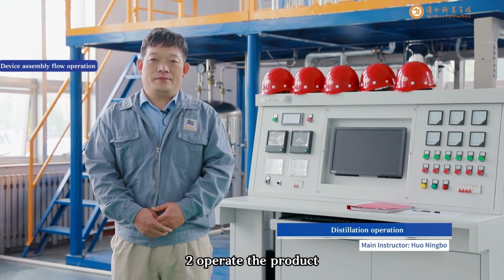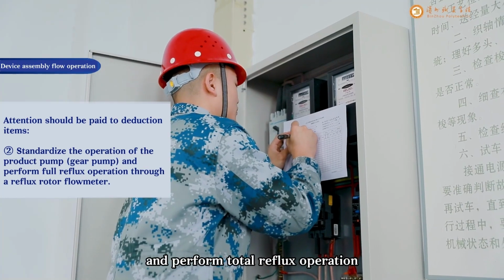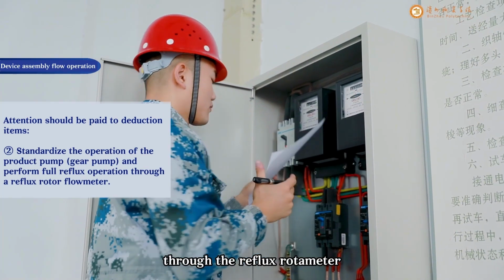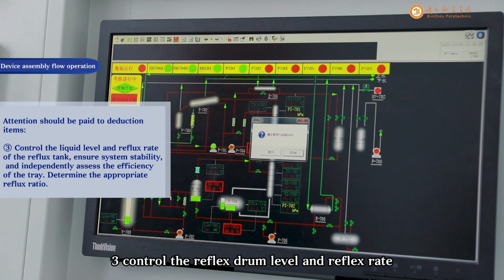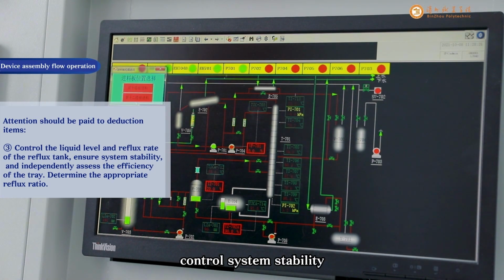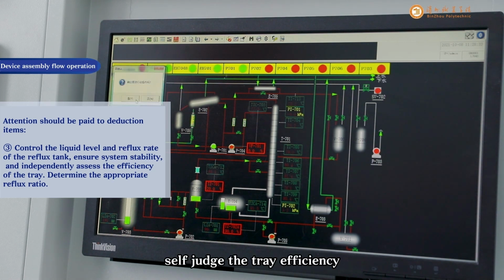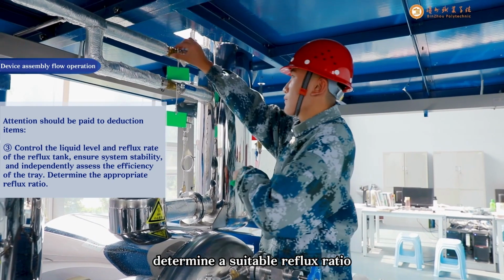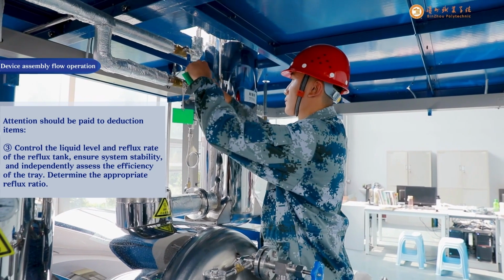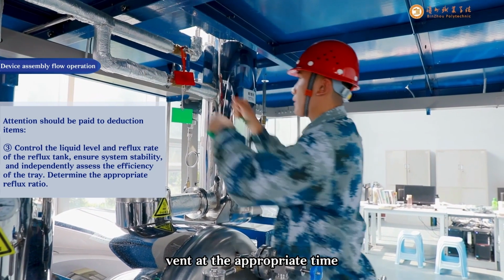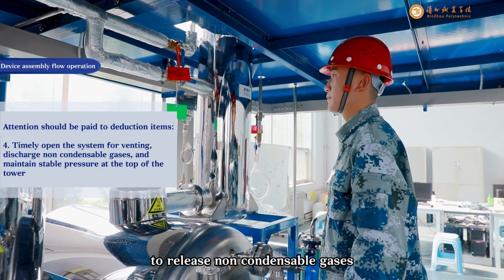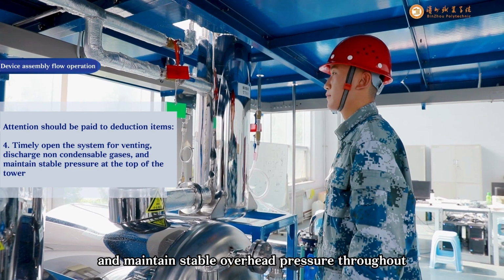2. Operate the product pump standardly and perform total reflux operation through the reflux rotameter. 3. Control the reflux drum level and reflux rate. Control system stability. Self-judge the tray efficiency. Determine a suitable reflux ratio. 4. Open the system vent at the appropriate time to release non-condensable gases and maintain stable overhead pressure throughout.